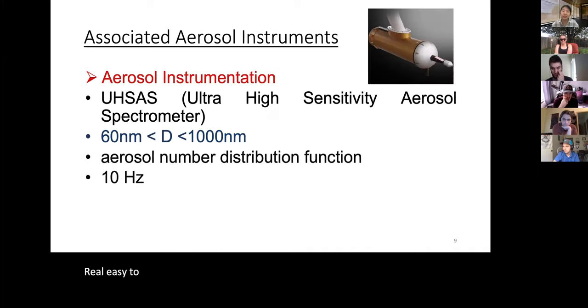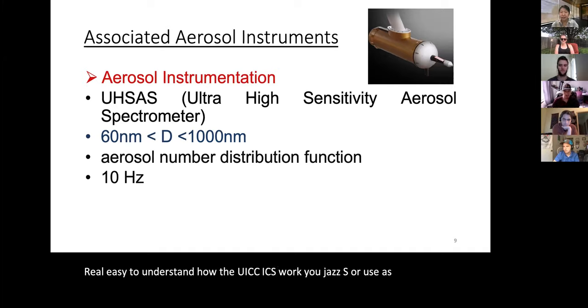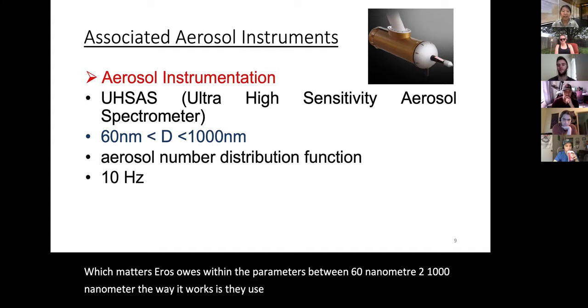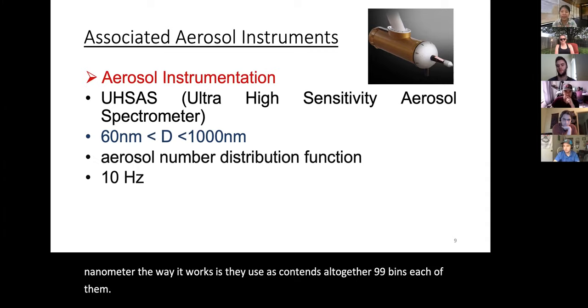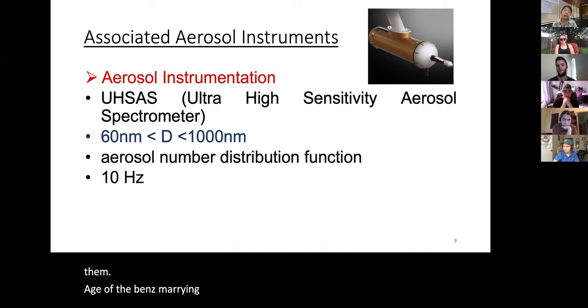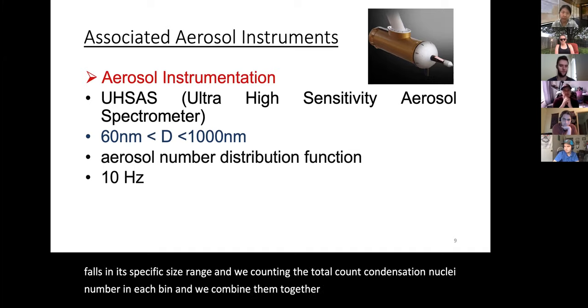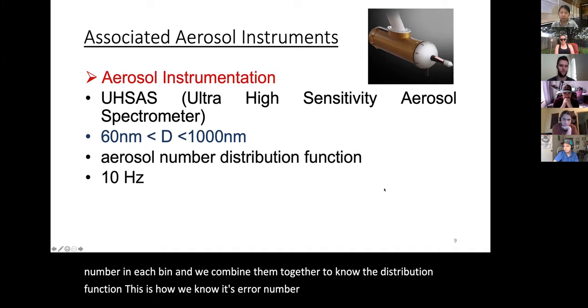The UHSAS — Ultra High Sensitivity Aerosol Spectrometer — measures aerosols with diameters between 60 nanometers and 1,000 nanometers. It contains 99 bins, each measuring a particular group of aerosols within a specific size range. By counting the total condensation nuclei number in each bin and combining them, we derive the aerosol number size distribution function. It operates at a 10 Hz frequency. The UHSAS covers only a portion of the aerosols captured by the CPC.